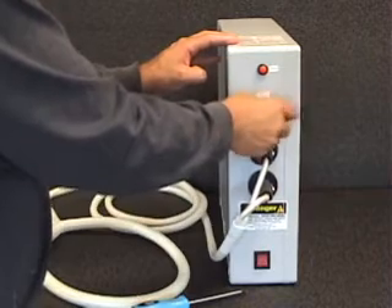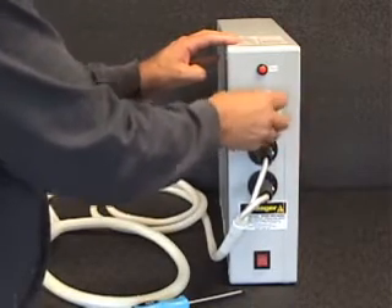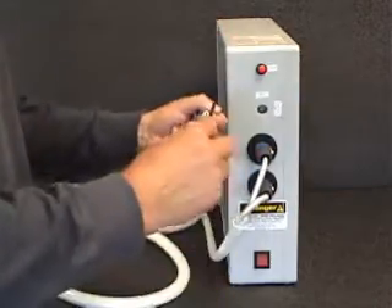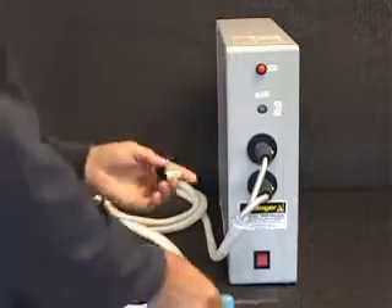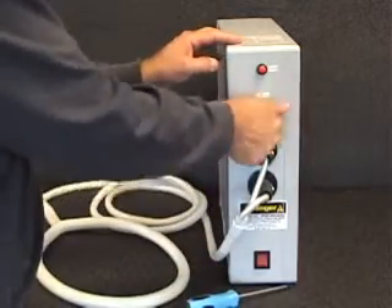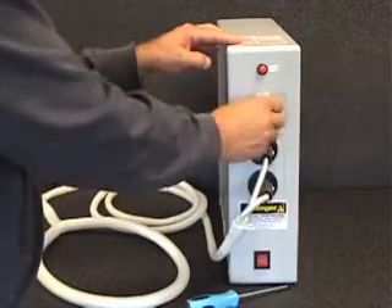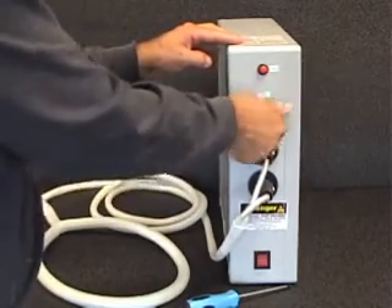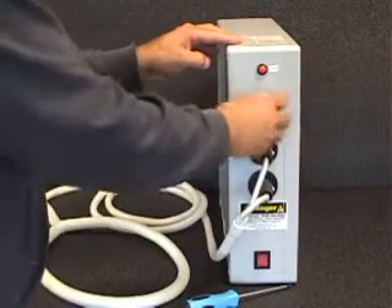Note that it isn't even necessary to turn the unit off when you pull this out. Basically, removing the screw causes it to just go to its maximum intensity. You can continue to adjust the internal set screw to the appropriate level. In this case, we're removing it again because we prefer an absolute minimum.